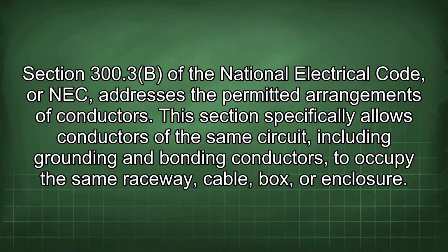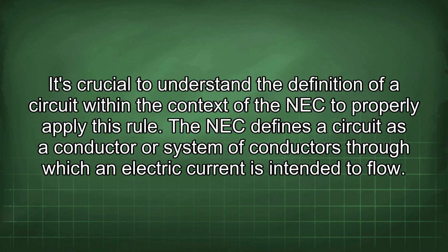Section 300.3b of the National Electrical Code, or NEC, addresses the permitted arrangements of conductors. This section specifically allows conductors of the same circuit, including grounding and bonding conductors, to occupy the same raceway, cable, box, or enclosure. It's crucial to understand the definition of a circuit within the context of the NEC to properly apply this rule. The NEC defines a circuit as a conductor or system of conductors through which an electric current is intended to flow.